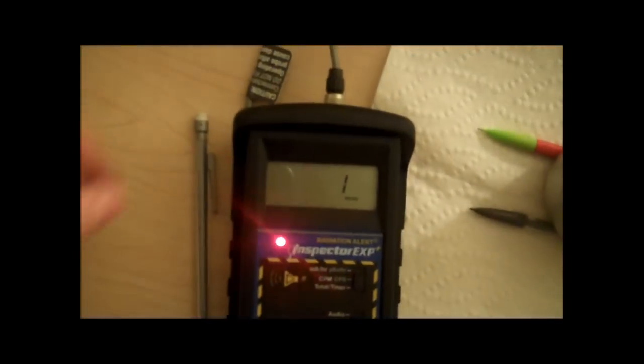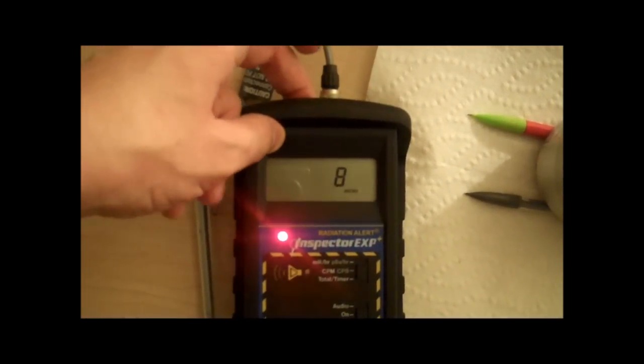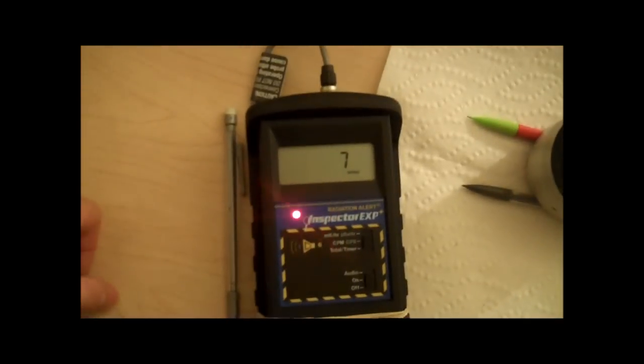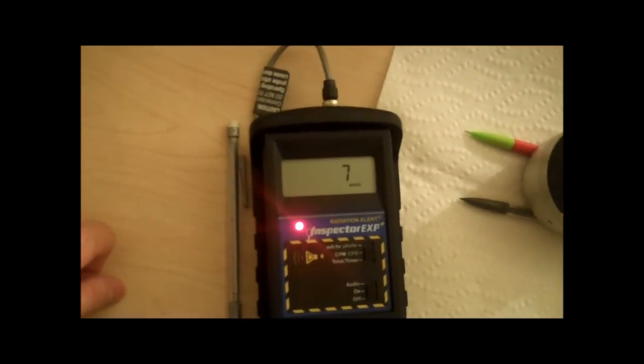Alright, so we're in the menu. It's going nuts over the polonium. Set to option 7. Option 7, not 8. 7 is the calibration factor. This is a coefficient multiplied by what this thing is normally detecting. Alright? So it's not going to mess up the factory calibration. You can reset it immediately. If you go to option 3 and hit the set button here, it'll go BAM right back to 100%.